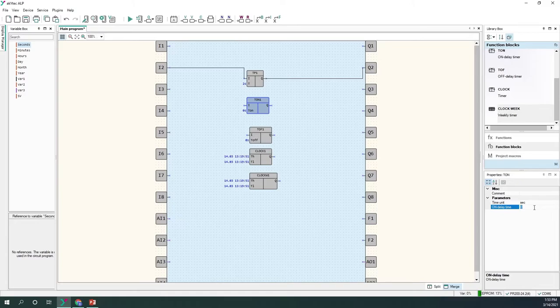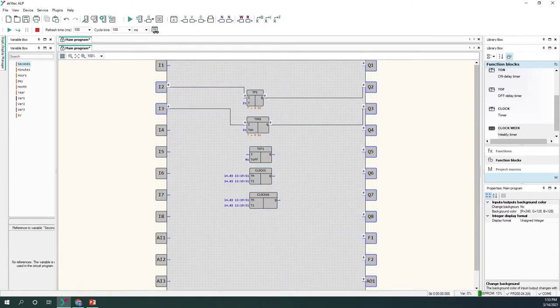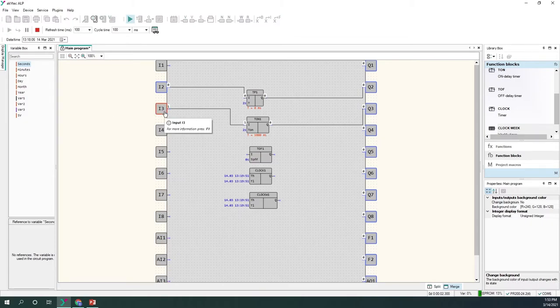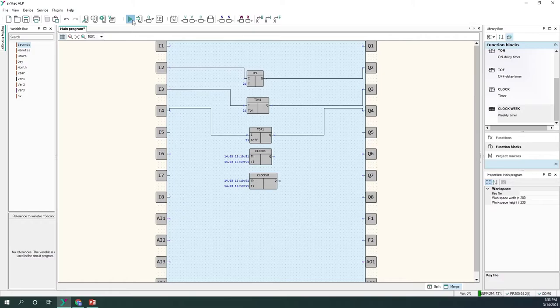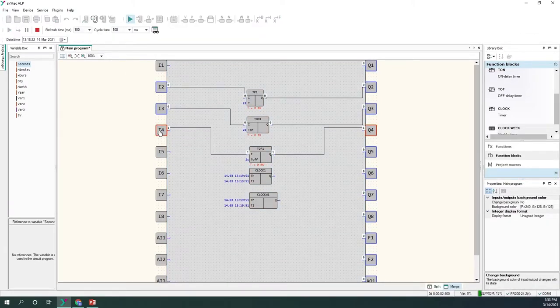The on-delay timer: I'll set it to two seconds. In simulation, the input has to remain high for at least two seconds for the block to output a one. For the off-delay timer, also set to two seconds: when the block detects a falling edge on the input, it starts a timer and the output will remain high for two seconds.